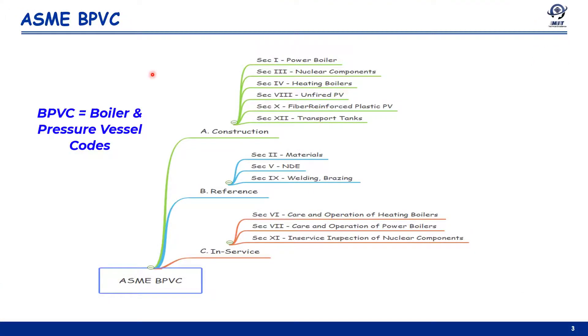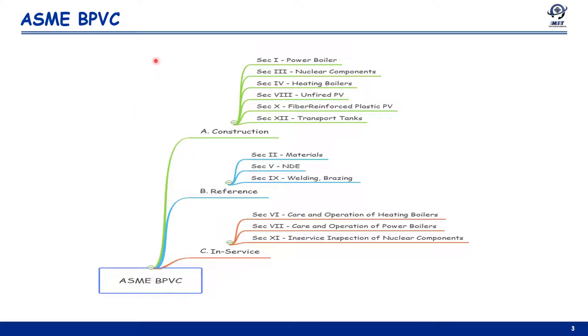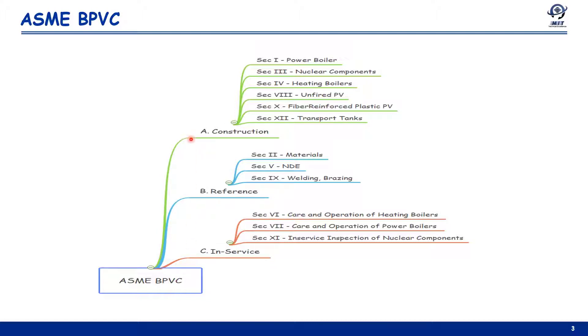BPVC, or Boiler and Pressure Vessel Codes, can be mainly categorized as construction codes, reference codes, and in-service codes. For construction and design codes, we have Section 1 for power boilers, Section 3 for nuclear components, Section 4 for heating boilers, Section 8 for unfired pressure vessels, and Section 10 for fiber-reinforced plastic pressure vessels.